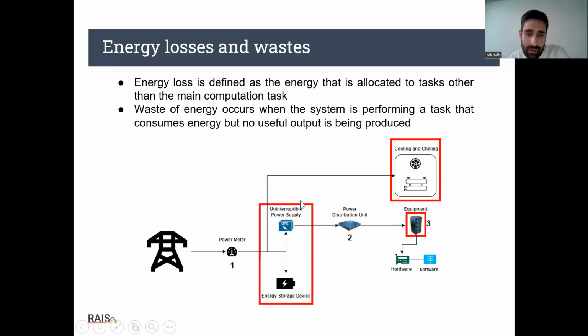On this diagram, you can see where losses and waste can happen. Typically, energy losses happen when charging the energy storage devices or the UPS, and the energy spent on cooling the IT equipment is also considered energy loss. Energy waste occurs within the IT equipment during idle periods of time. Also, points 1, 2, and 3 represent where energy measurements can be performed at different levels within the data center.